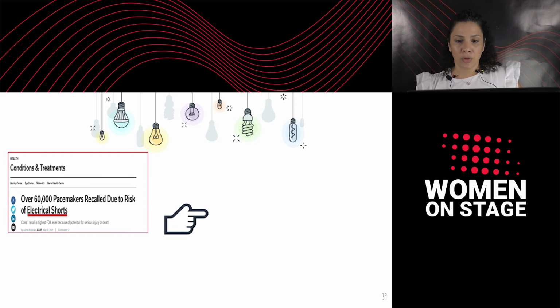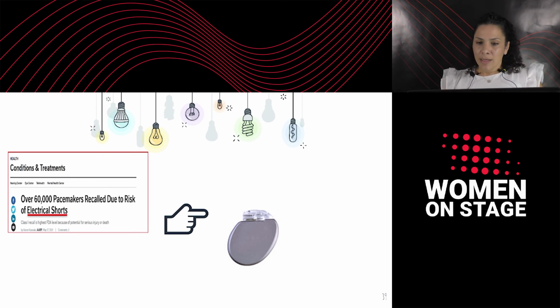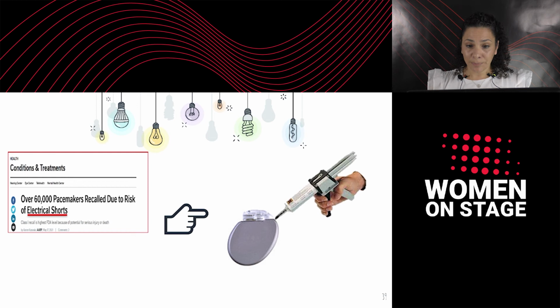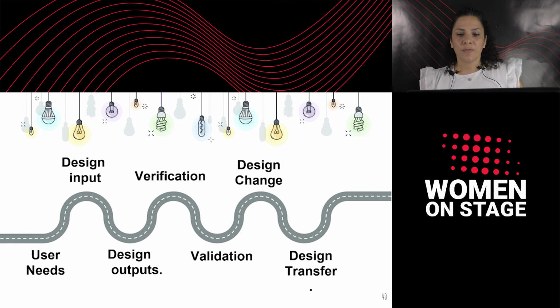First, I will remind you that the pacemaker was recalled from the market due to risk of electrical short. Now, I want to share with you that the company found out that the electrical short appeared due to moisture inside the device. And last, we should know that the moisture in the device appeared due to an integrity failure related to the epoxy glue. Knowing those facts, let's get back to our journey and revisit stations in order to try to identify where things could go wrong.